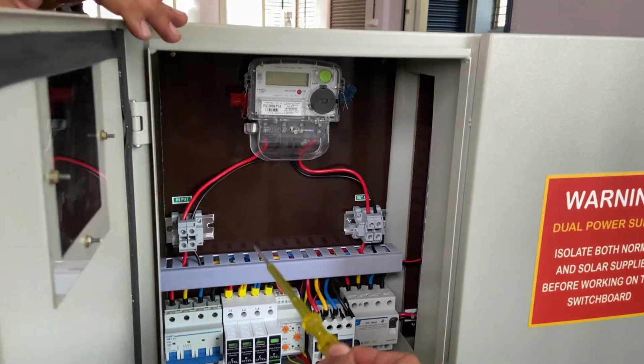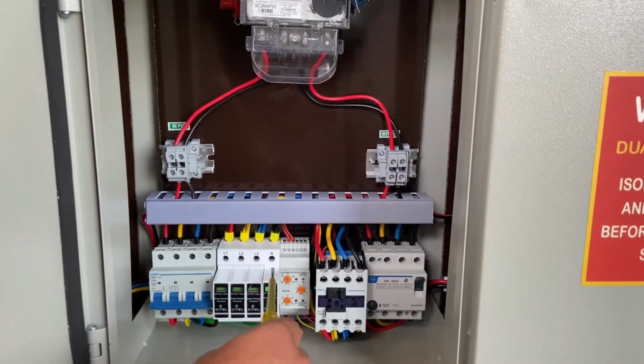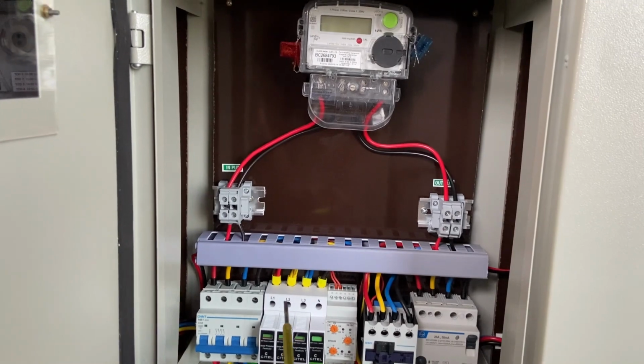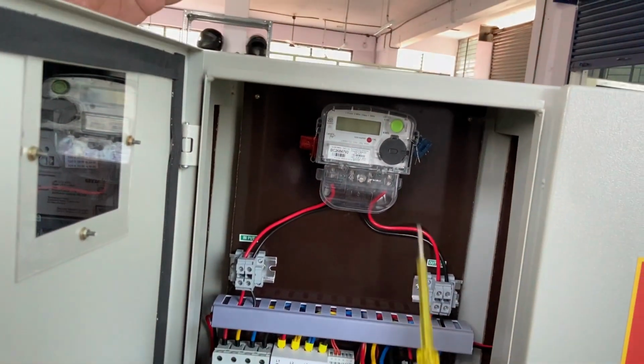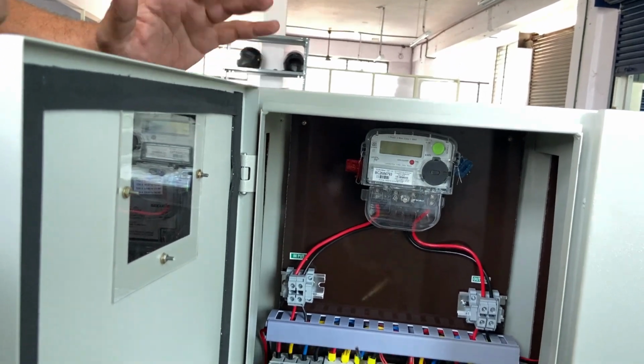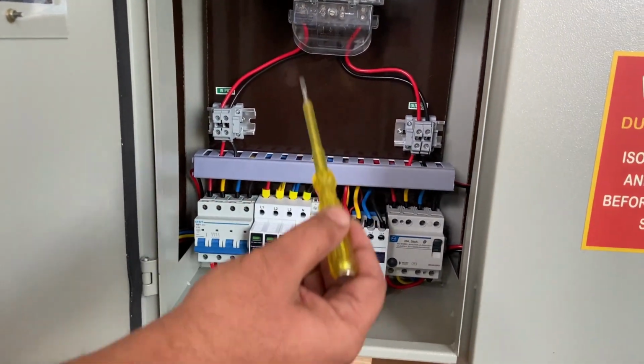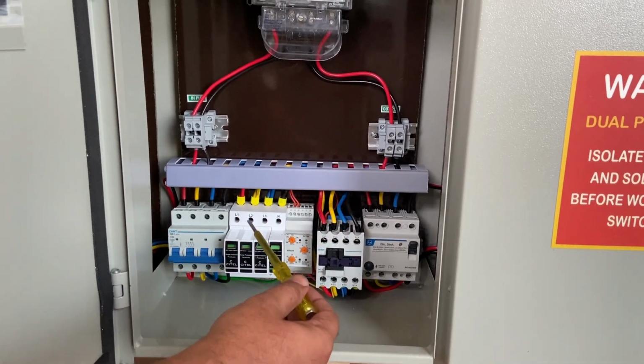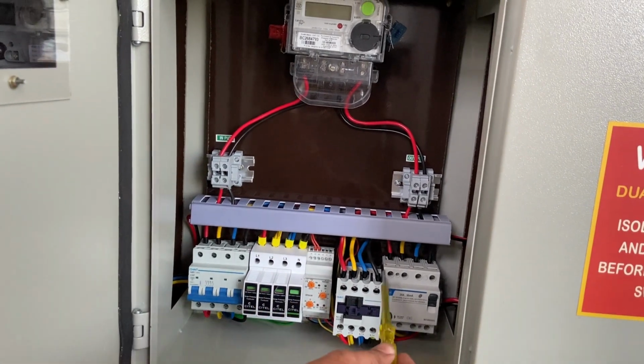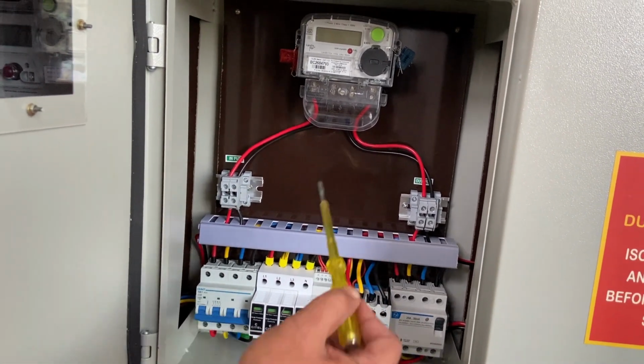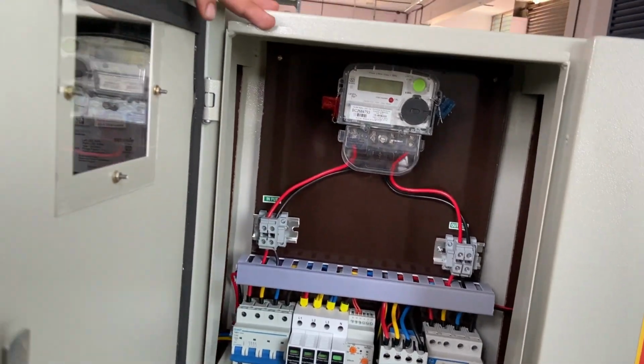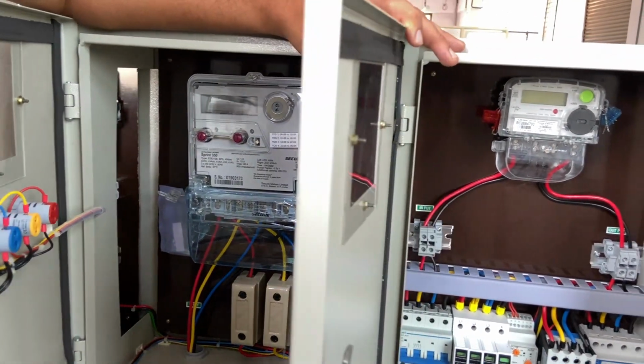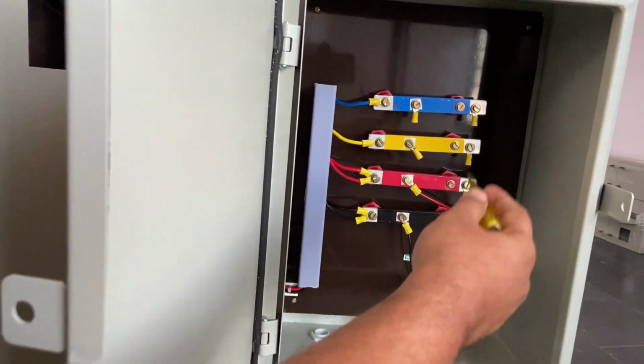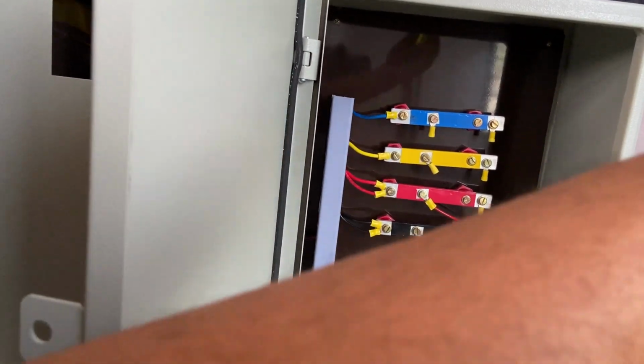On the utility side, before it gets into the loads, we install type 1 SPDs or type 1 plus 2 SPDs. Type 1 SPDs are installed at the mains. The main function of these SPDs is to sense the transient voltages or surges and ground them. So it is very important to have a type 1 SPD at the utility point. Again, we have a contactor and a relay. We have an ELCB. So the power from our main meter goes into all these protections and then gets into the load bus bar. This is where the power is distributed into the business or into the house.